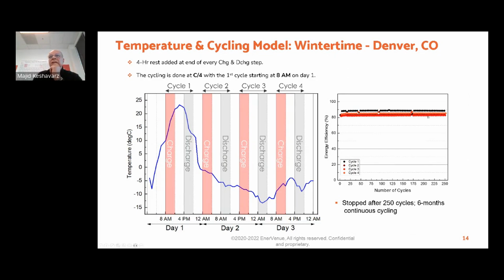Again, the results you can see it's very impressive. Flat line, you can tell the difference between cycle 1, which is in a warm day, and the third day is the coldest. That's the bright red dot, and the other 2 cycles in between, again, very predictable and works well at the -13 degrees C. I should note that technologies like LFP is not recommended even to charge below 0 degrees C. These type of batteries work really well at even cold temperature.